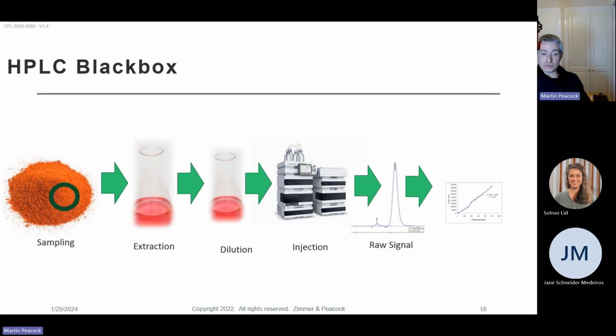When was that calibration last run? Was that HPLC system calibrated 1 day ago, 1 week ago, or 1 month ago? Now, I know what happens, I think, in HPLC test houses: they save up the samples, they do a calibration, then they run the samples. So sometimes part of the delay is that they do want to do a good job and they want to calibrate the instrument. So they can't just calibrate the instrument and run one test. No, they would have to build up a few samples and then calibrate, and run all those samples whilst the instrument is still within calibration.